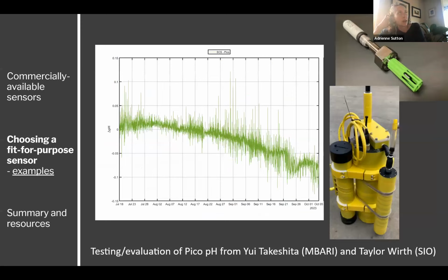Taylor and Yui have also been testing the drift rate. The company reports a drift rate of less than 0.005 per day at a pH of 8 and 25 degrees C. But really the user is on the hook to figure out whether that's consistent in the specific conditions they're working in that have more variability. So Taylor deployed a new Pico pH sensor next to a sensor that is well characterized and calibrated in situ. And they measured a drift rate for the Pico of about 0.001 pH per day in these summer and fall conditions typical of the coastal environment near their lab. And that's something they will have to account for in their post-processing of the data.